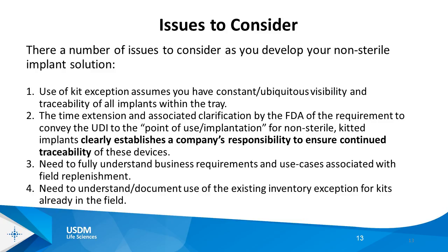I know a number of manufacturers have used the convenience kit exception to identify a kit. And FDA has said that things like medical procedure trays are kits. So a number of manufacturers have said, okay, I'm using the kit exception. I'm putting a UDI on my tray or my caddy, and that's fine.